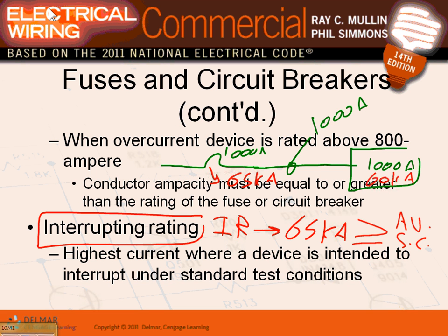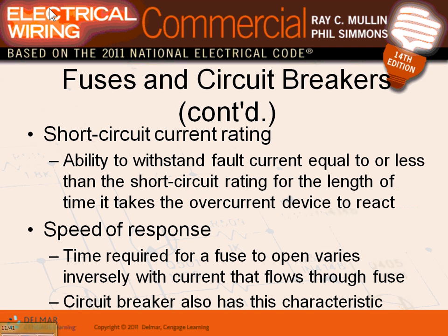You guys are going to be doing calculations next quarter based on short circuit calculation. Short circuit current rating. Okay, this is what we just talked about, guys. The withstand current rating must be equal to or more than the short circuit current rating for the length of time it takes the overcurrent device to react.